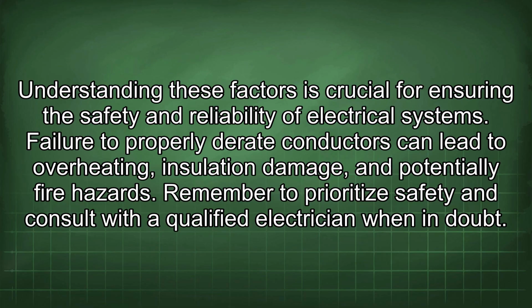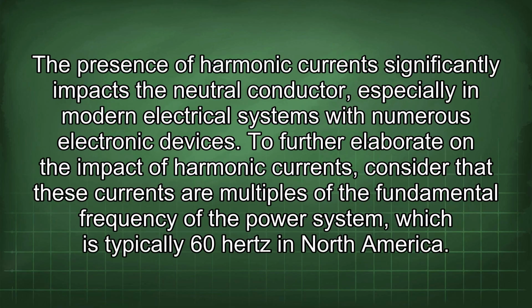Understanding these factors is crucial for ensuring the safety and reliability of electrical systems. Failure to properly derate conductors can lead to overheating, insulation damage, and potentially fire hazards. Remember to prioritize safety and consult with a qualified electrician when in doubt. The presence of harmonic current significantly impacts the neutral conductor, especially in modern electrical systems with numerous electronic devices.